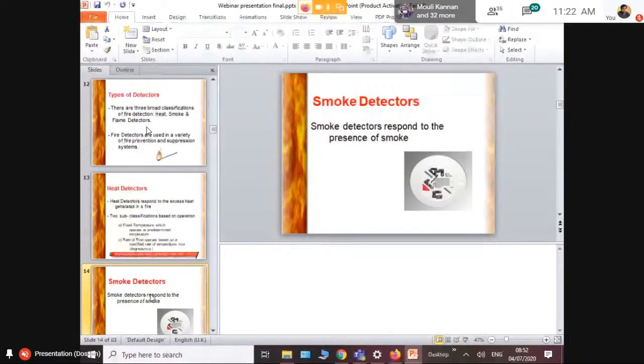So if you see the smoke detector here, this is how it looks. Smoke detectors work on 24-volt DC. So you'll have a positive connected here, a negative connected here, and you'll have the earth wires connected here. It's the same for all the devices, smoke, heat, or any fire alarm device: positive, negative, and earth. All these have to be wired properly without any open and short circuits.